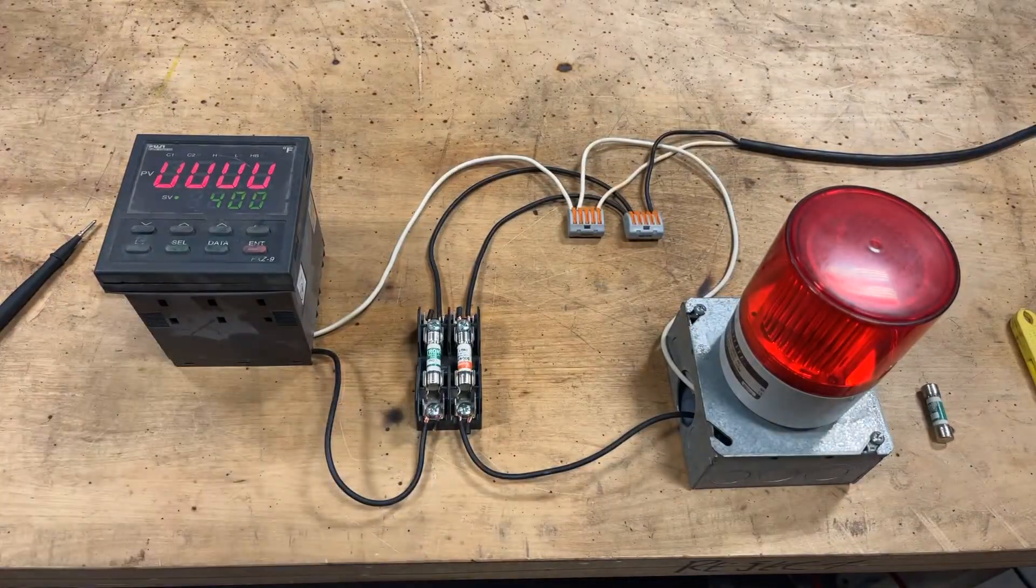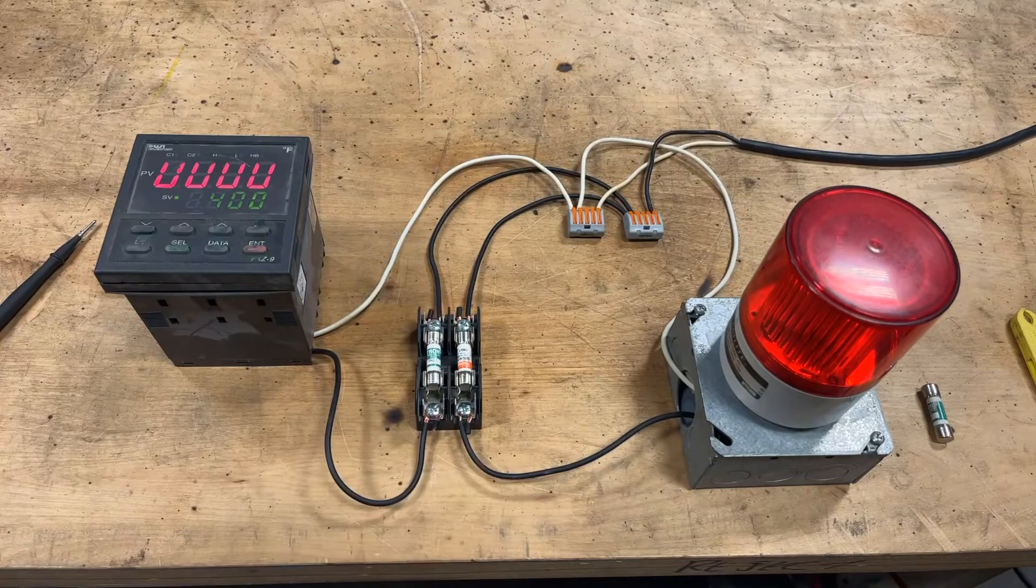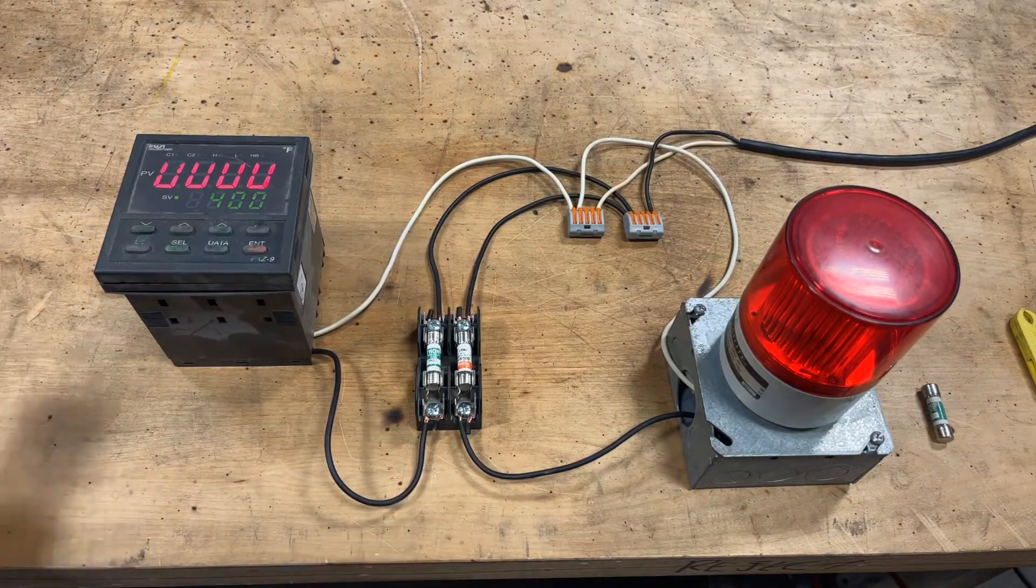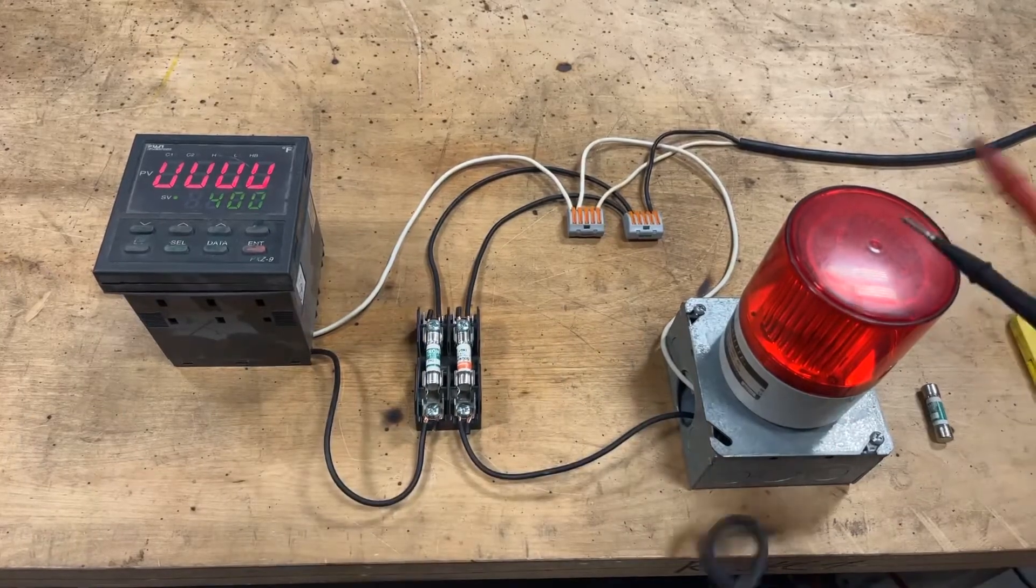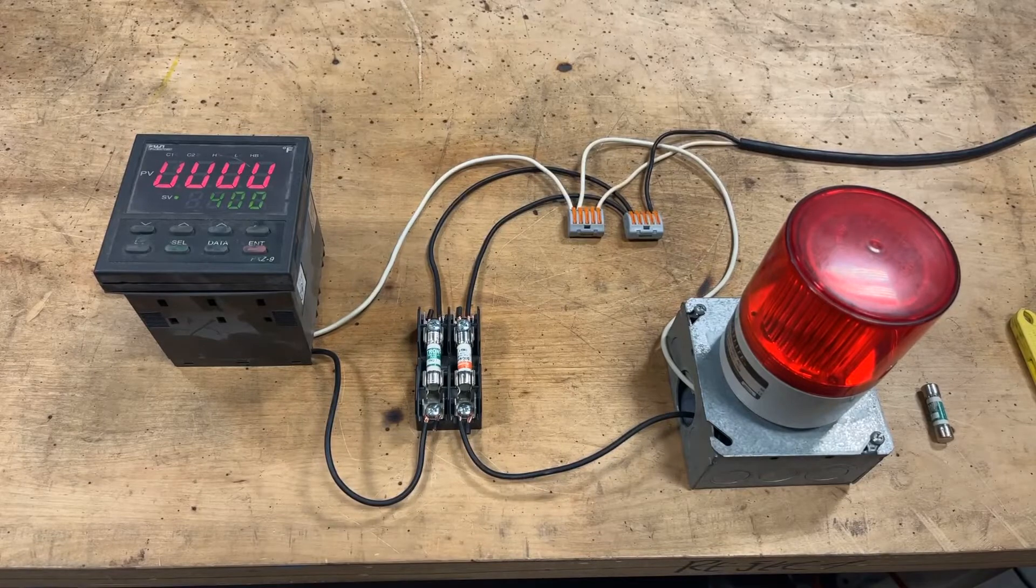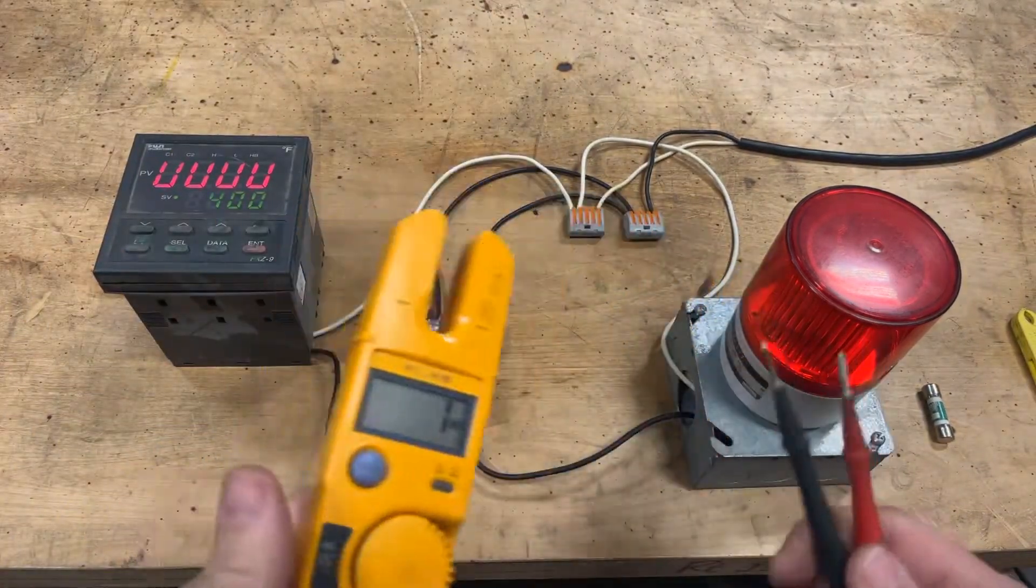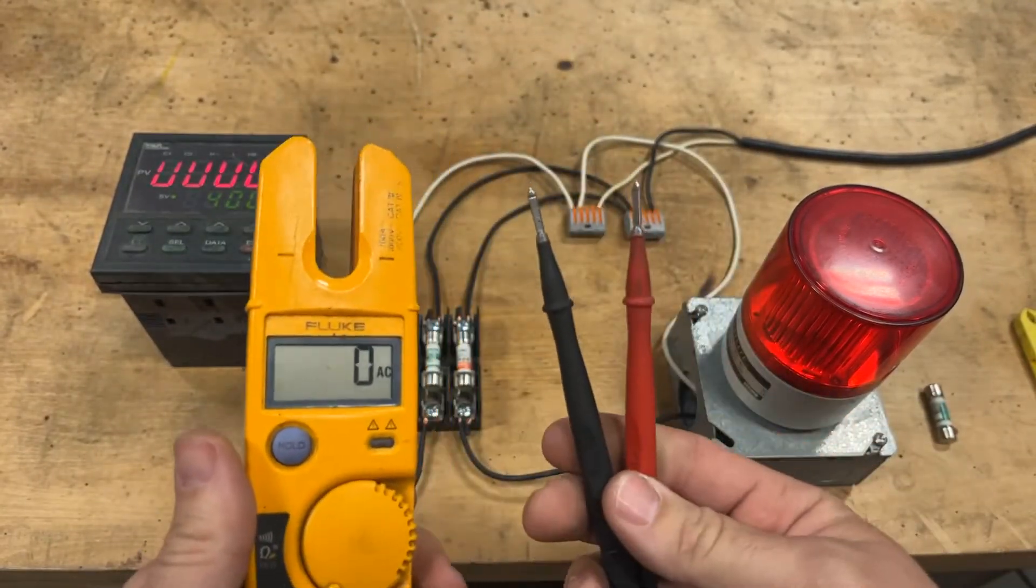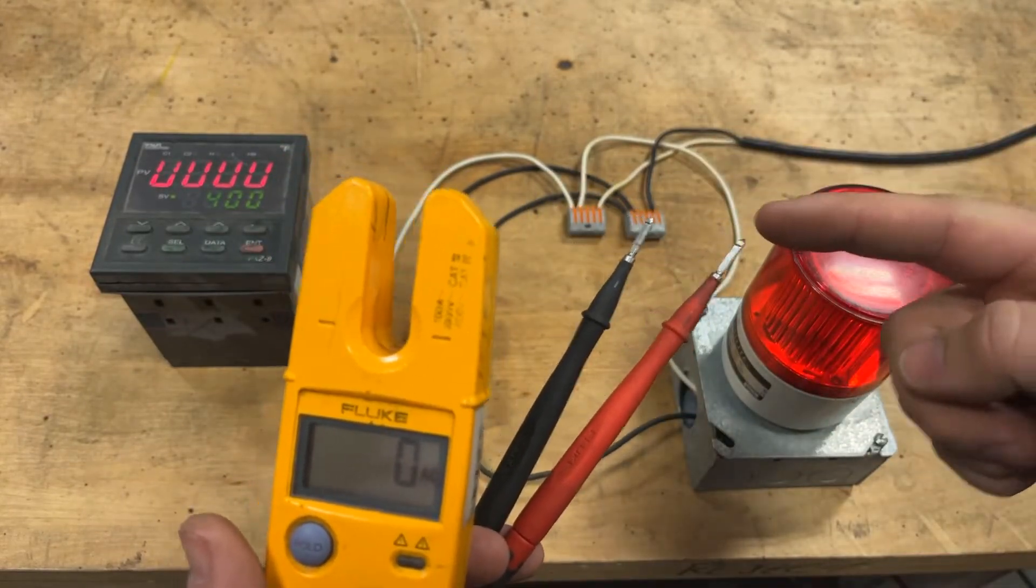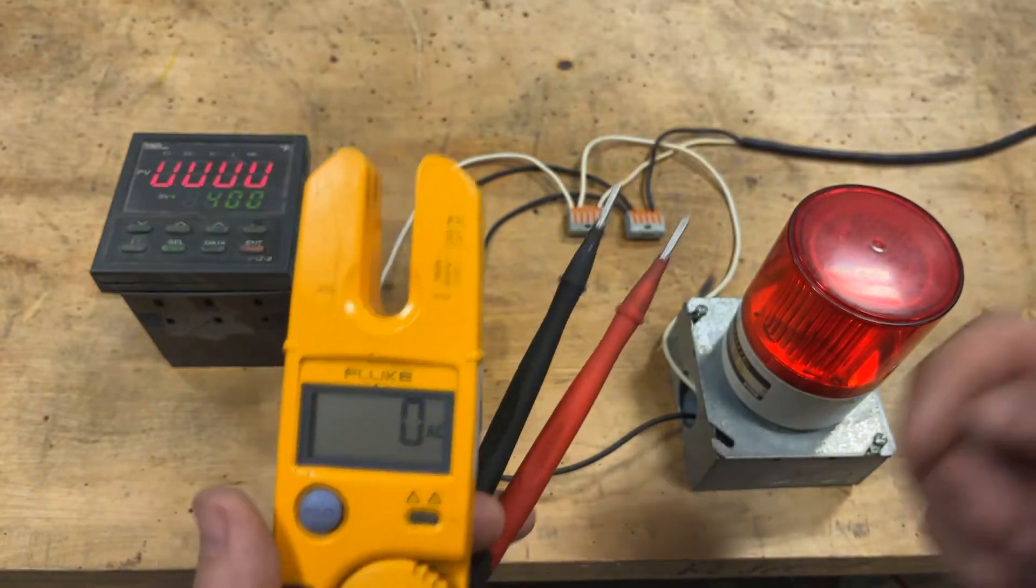So right now we have a live fuse and a dead fuse. By the way, this is super common - to have a fuse block running off a bus so you can have multiple distributions of power from one source. To be safe, you'd want to de-energize this circuit to check that fuse by ohming it out. But in this case, we can't power down this super important computer because Skynet will take over the world, but I need to check the power source for this light to get the system operational again. If you take your meter and put it to voltage, voltage on a multimeter checks differential between one probe to the other. That means there has to be a difference in voltage from one probe to the other - power on one and none on the other, or a difference between the two.